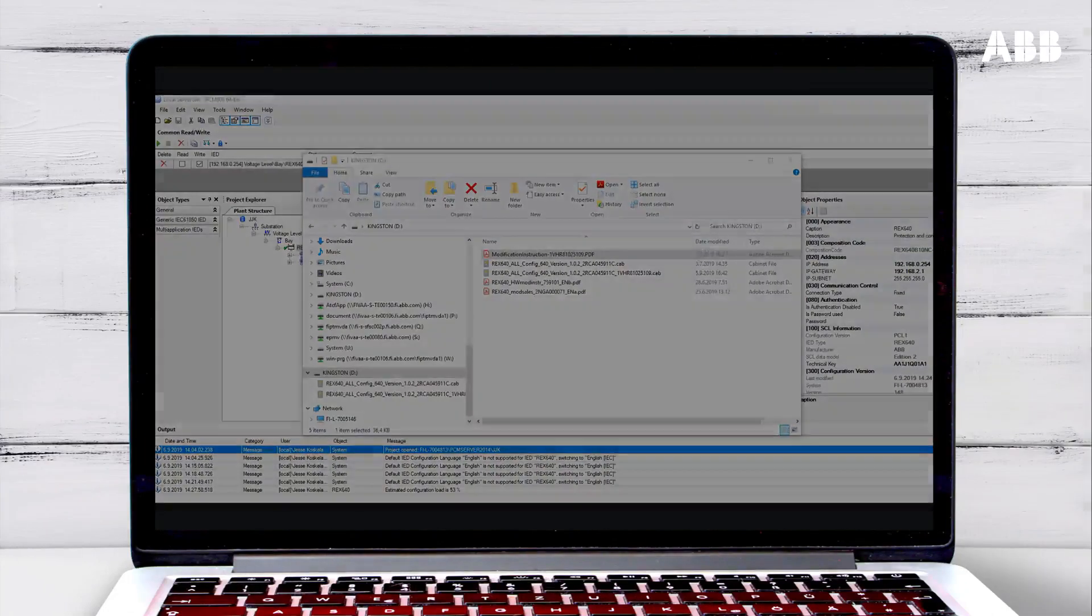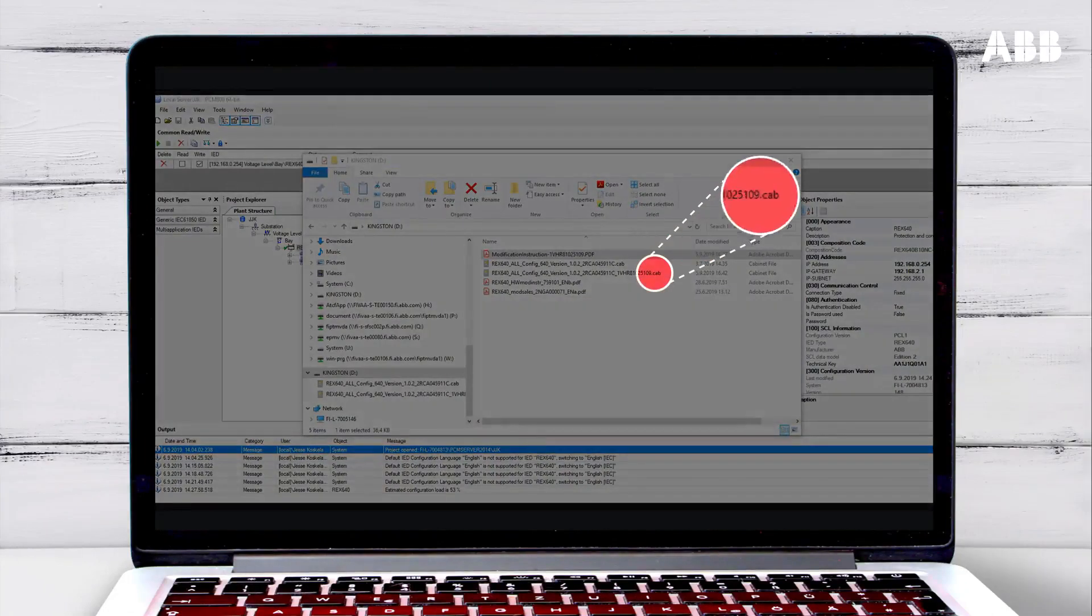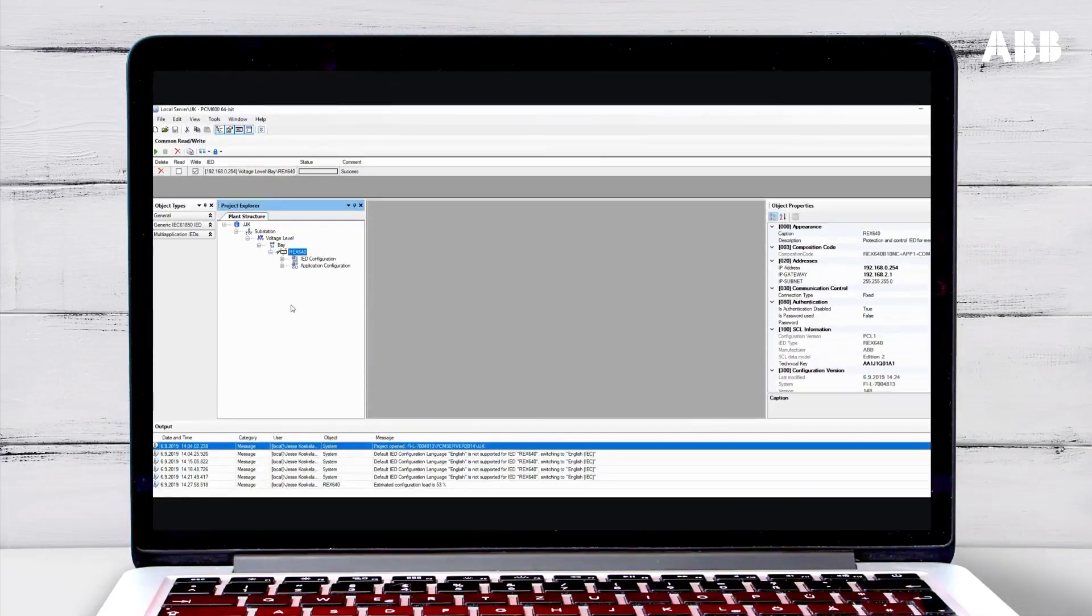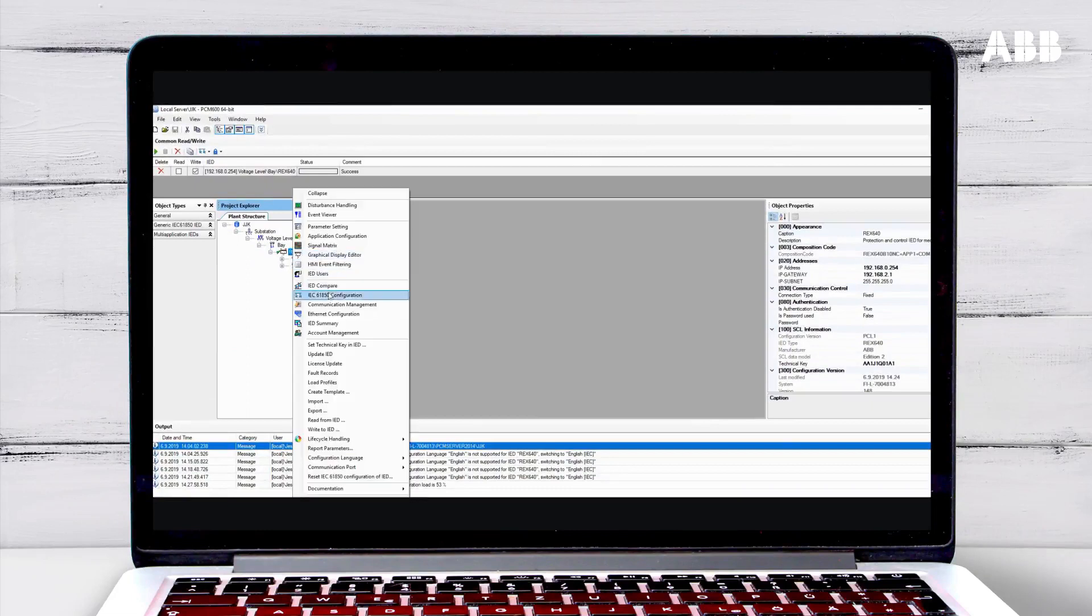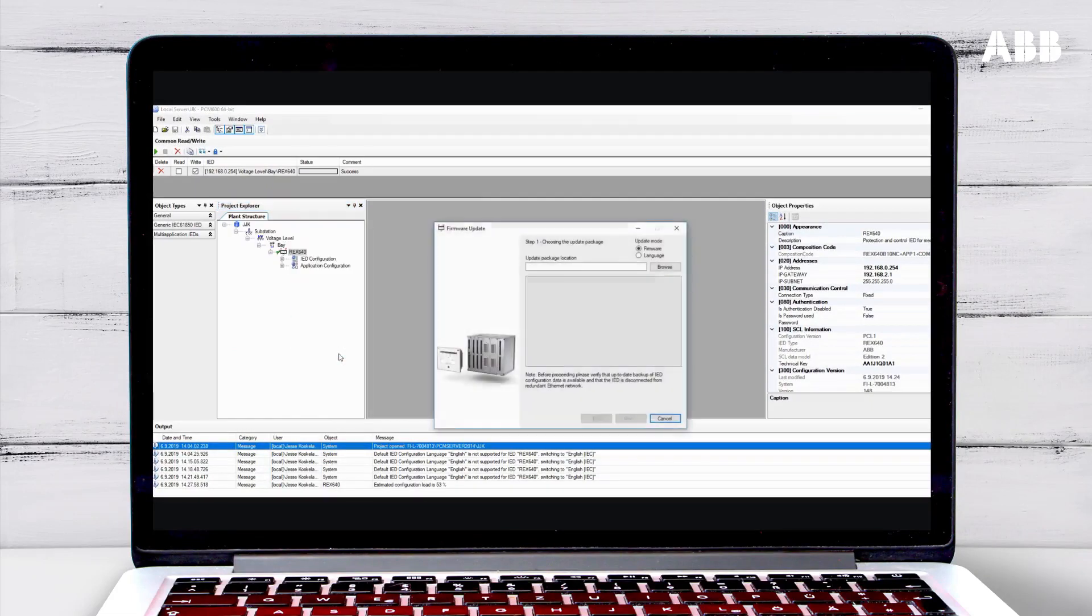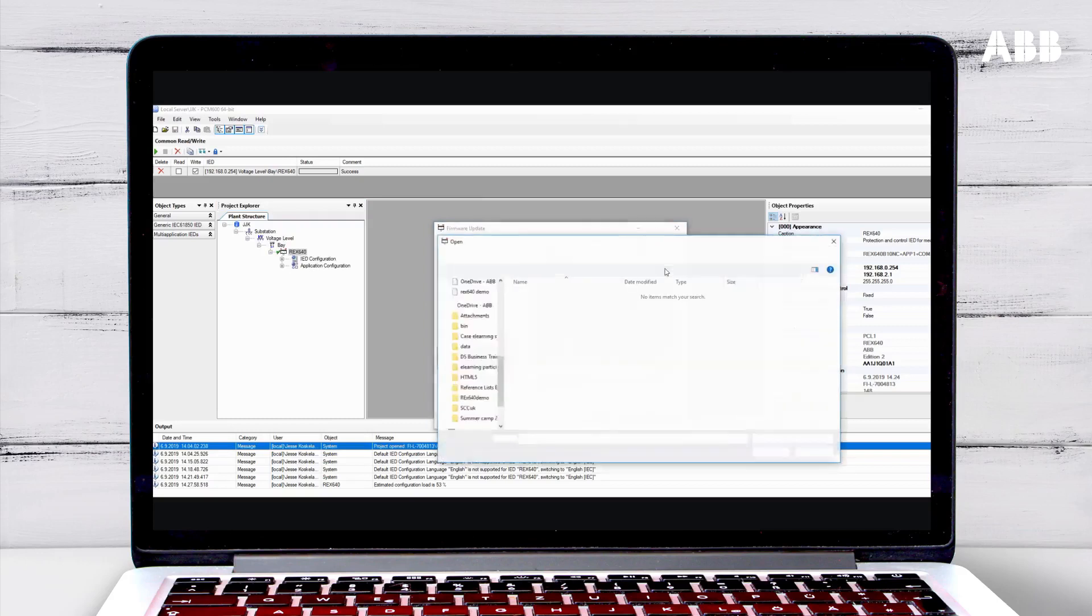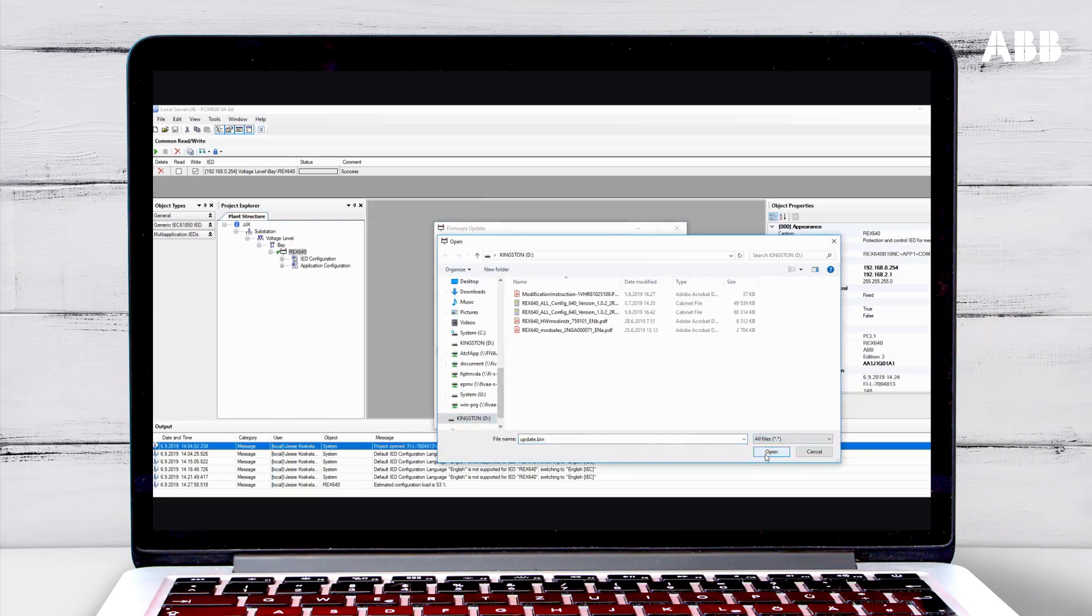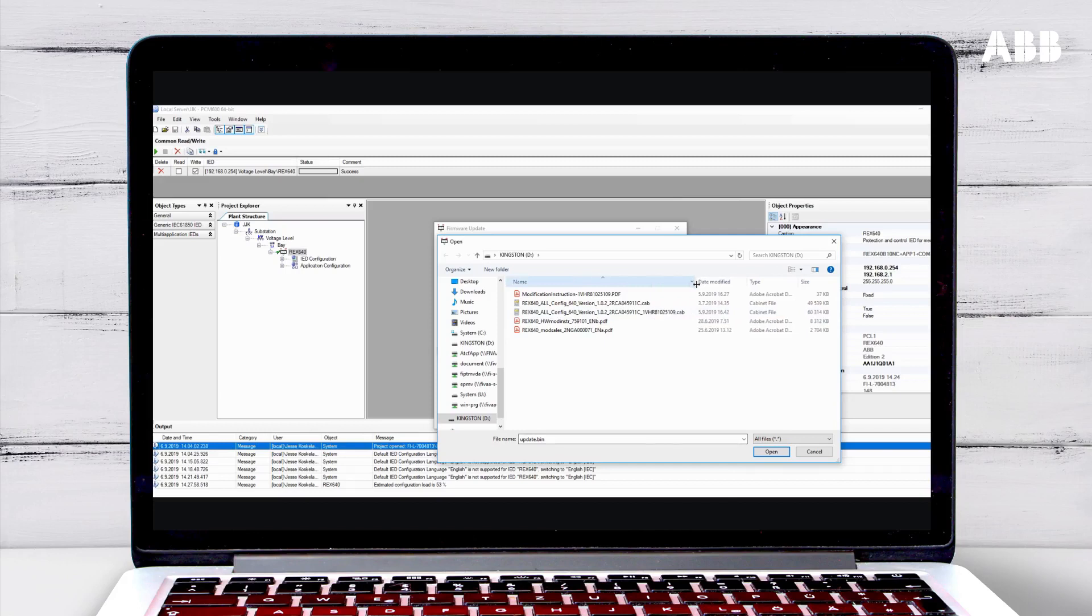The software package is delivered as a .cab file. To install the software, connect to the relay in PCM600, then right-click on the relay and select Update IED. This will start the update wizard. Select the update file by clicking Browse and navigating to the .cab file. You may need to change the file view settings so that you can see all file types.